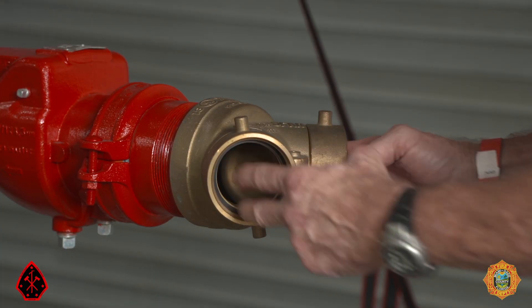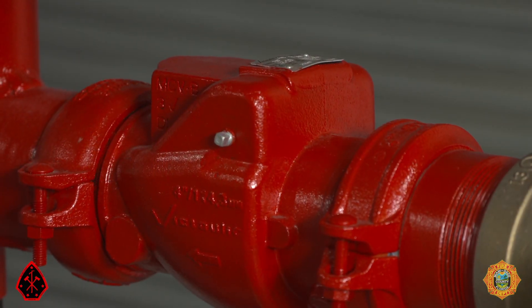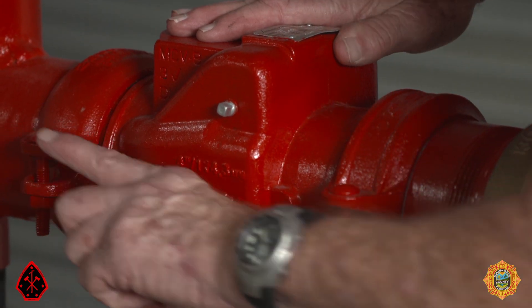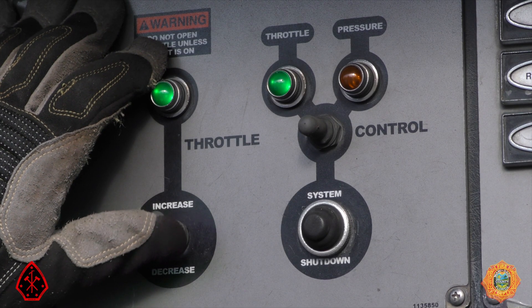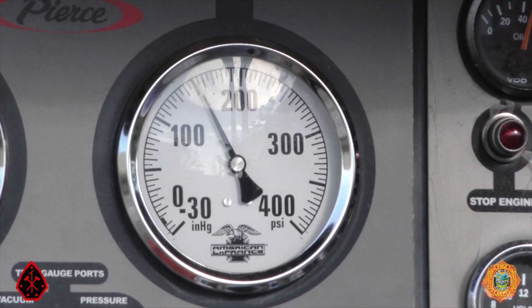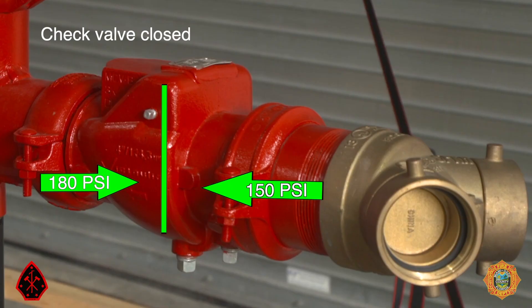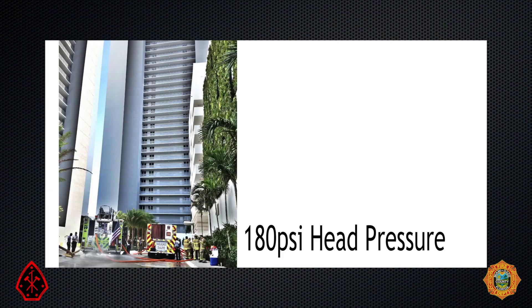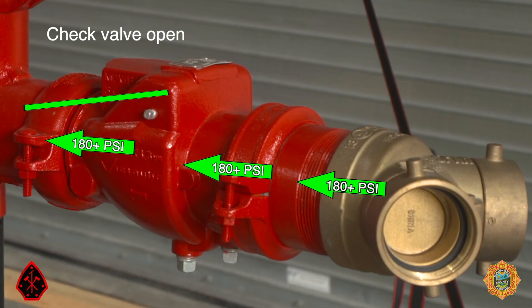There is a one-way check valve between the fire department connection, the FDC, and the base of the risers. If an engine was to pump 150 psi into the fire department connection, it would fail to push open the check valve. The engine would have to increase its discharge pressure to over 180 psi in order to force open the check valve and get water in the system, even if the fire was on a lower floor.